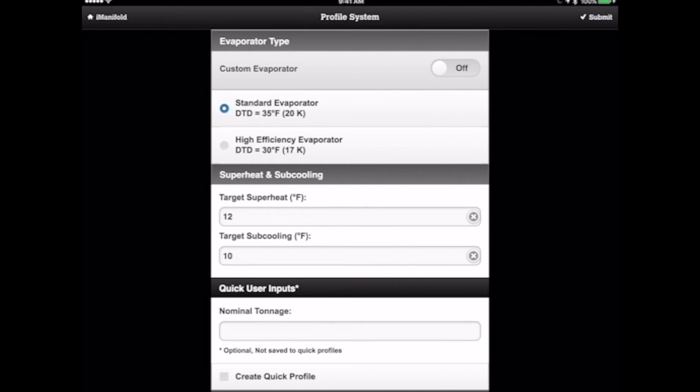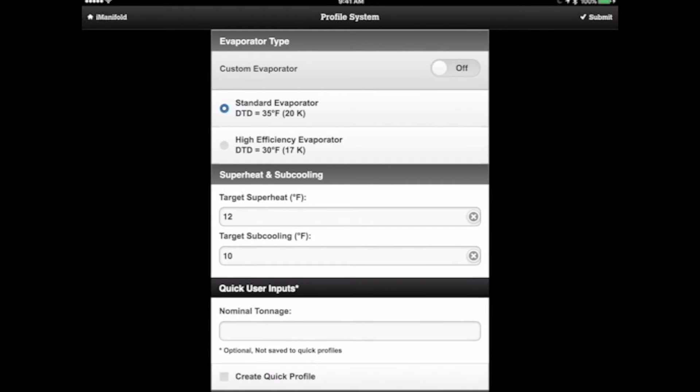Now, the next thing we need to do is determine our target superheat and target subcooling. Well, again, this is a TXV system. So we expect to see somewhere between, usually between probably 8 and 20 degrees of superheat. Typically I'll set these at about 12 degrees for the superheat setting. But let's find out what the manufacturer requires for target subcooling.